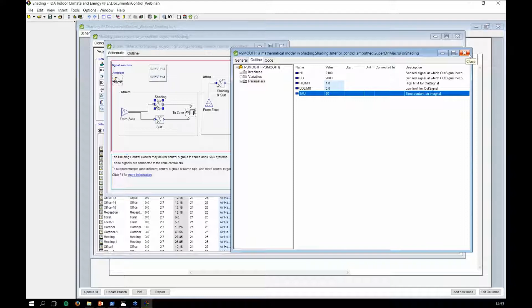What is this tau? That is what I wanted to introduce in this case. Basically, this tau is the time constant that you can put as a low-pass filter on the in signal. When your in signal is noisy, or has a dramatic change in a very short amount of time, you can filter this signal before giving it to the proportional controller. So in the base case, I'm not filtering my signal. In this case, I'm putting a 60-second time constant on the low-pass filter, and we're going to see what dramatic effect it has on the output. I'm putting a 60-second tau on basically the 3 proportional controllers. That's the only difference between these two cases. I'm calling this one control smoothed, because the input signal is smoothed or filtered. There's no noise in it.